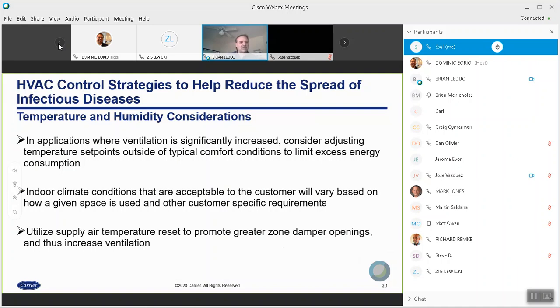Obviously, that's going to vary based on the customer, the space, how it's used. You can make use of supply air reset. What that will do for you in a zoning system, if you will, is it will promote greater damper openings. So if the air coming down the line is a few degrees warmer than normal, the zone dampers will open more. That'll increase ventilation, which again is one of the goals of the ASHRAE guidance.